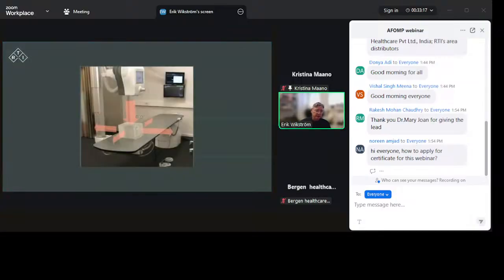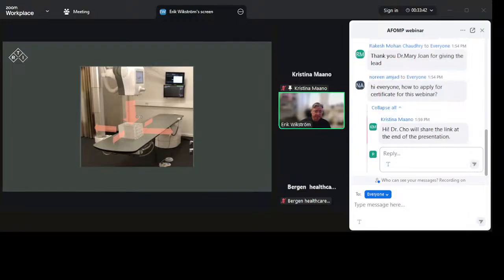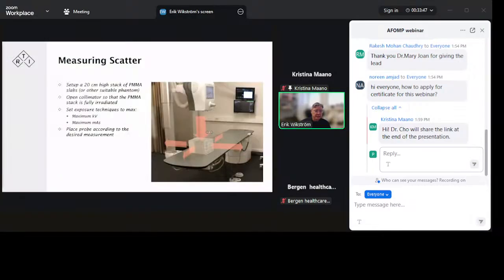Then when looking at scatter, that's a little bit of a different occupation. Like Christina was saying, it is the scatter generated by the secondary, so it's a secondary radiation. It's generated by X-rays, a primary beam hitting a subject, and from there we get scatter, and it scatters in different directions. And so we need to generate scatter in a standardized way when we're doing this testing.